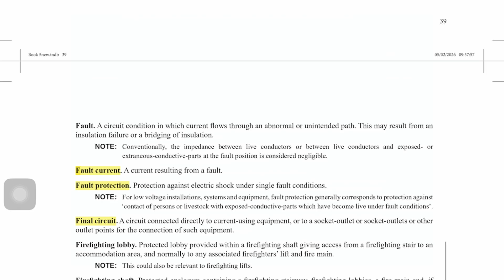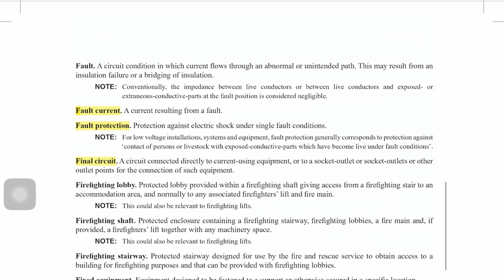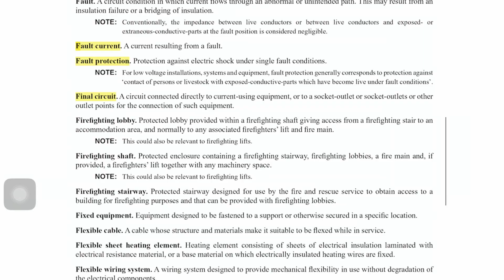I've highlighted final circuit there. That's a different type of circuit. I don't know if you call these at your place, but you probably don't have them as ring mains. A ring main connects between 11 kV transformers, and they connect up around factories, universities and hospitals. In a domestic dwelling, it'll be a ring final circuit because it's the last part of it.